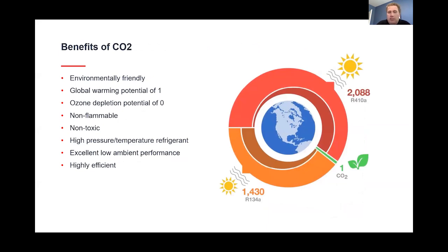So why do we use CO2 refrigerant? It's a great natural refrigerant that performs very well in high flow, low flow, high delta T situations, which is what we have here with the domestic hot water heater. It's got a GWP of 1, an ozone depletion of 0. It's non-flammable, non-toxic, high pressure temperature refrigerant, excellent low ambient heating performance, and highly efficient.